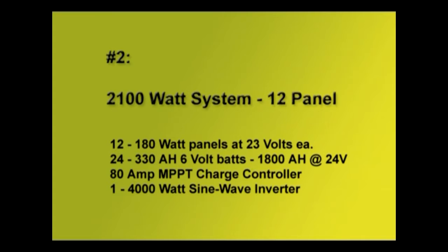Our second system is about a 2100 watt system using 12 panels. It has twelve 180 watt panels putting out around 23 volts each. It uses twenty-four 330 amp hour, 6 volt batteries, arrayed for 1800 amp hours at 24 volts. It uses an 80 amp MPPT charge controller and one 4000 watt sine wave inverter.